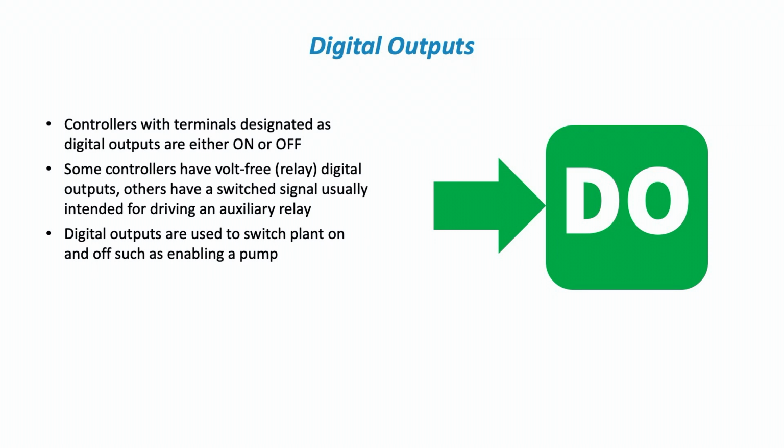Some of them have volt-free digital outputs. That means it's a relay, the relay clicks in, which means that whatever you connect to it has to supply the voltage. The relay itself is free of any voltage. You need to be careful when you're using these because some will switch mains voltage, some will not, but this is down to the individual manufacturers. So it's very important to read the instructions, or else you could potentially set fire to ASDAs in Clapham. I'm just saying, just putting that out there.